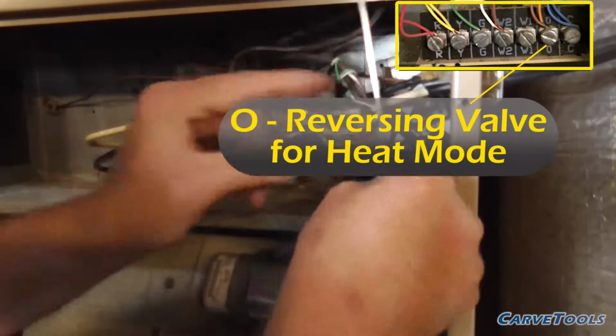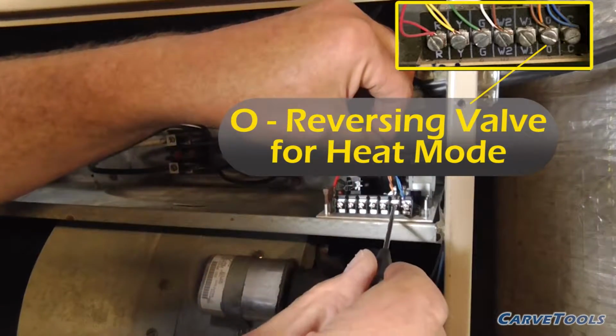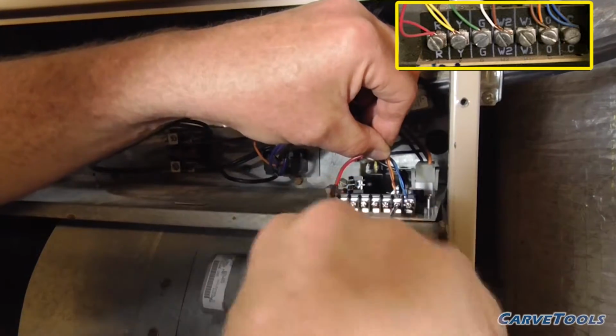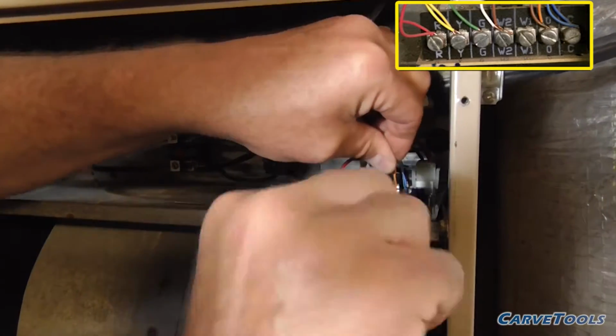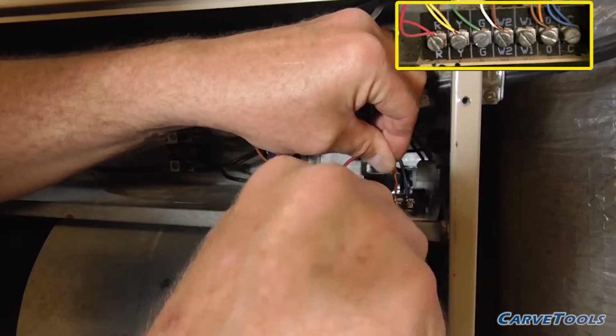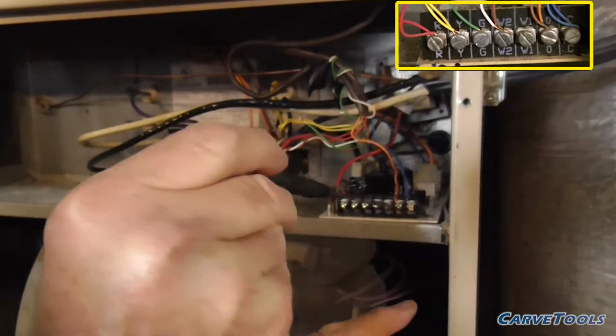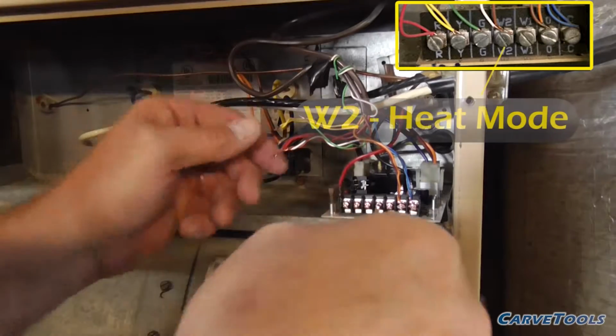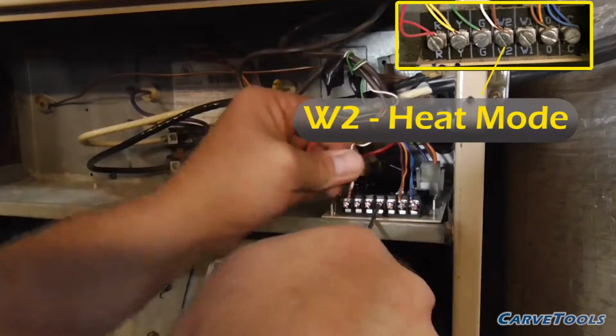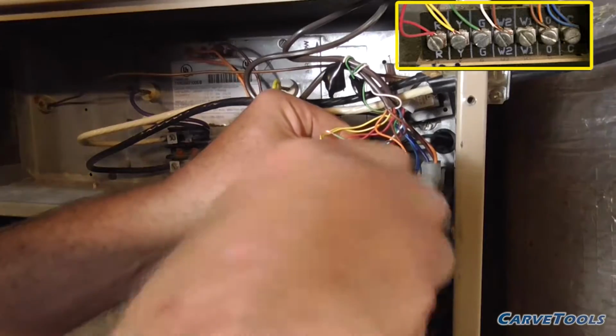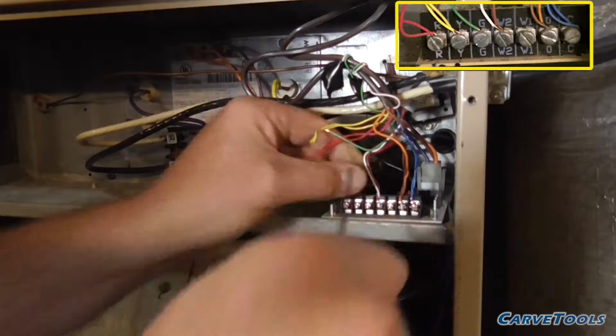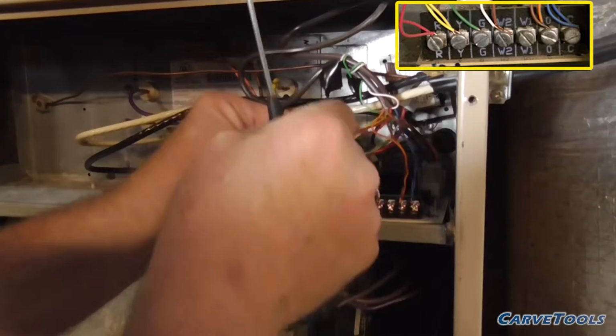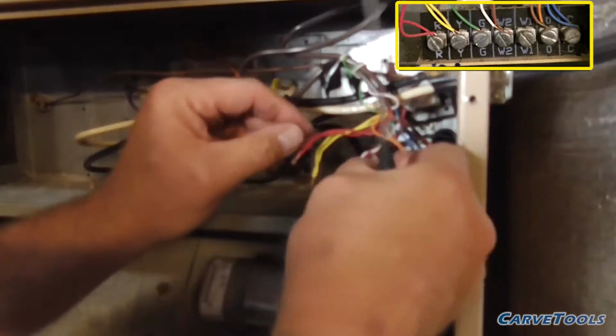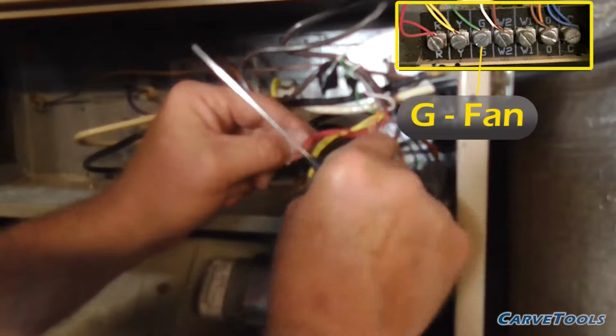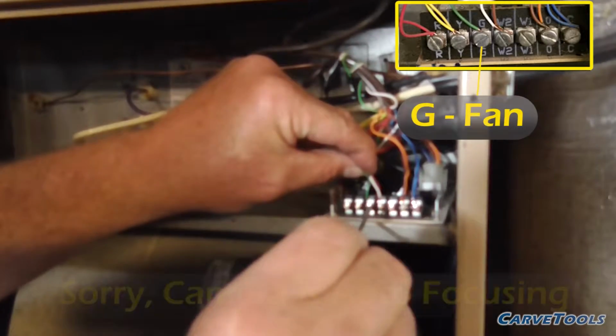Now this is a heat pump with auxiliary heat strips, and there are two wires twisted together. One is orange, one is brown. One wire goes to the outside unit. That operates the reversing valve, and the other goes to the thermostat. The W2 terminal is for heat mode. Now brown is the normal color, but here the brown and white are tied together. Once again, one is from the thermostat, the other is to the outside unit, and it goes through this control board. The G terminal is a single green wire, and it's from the thermostat, and this is what controls the blower fan.